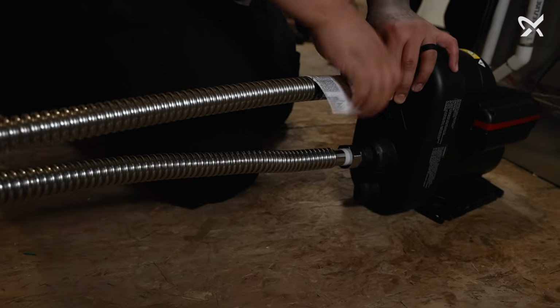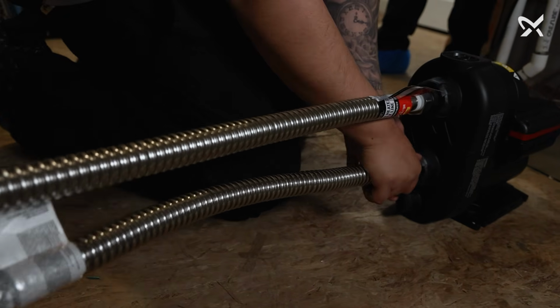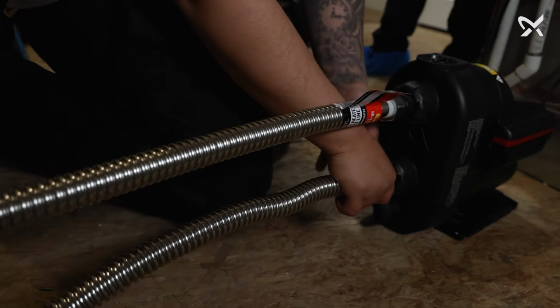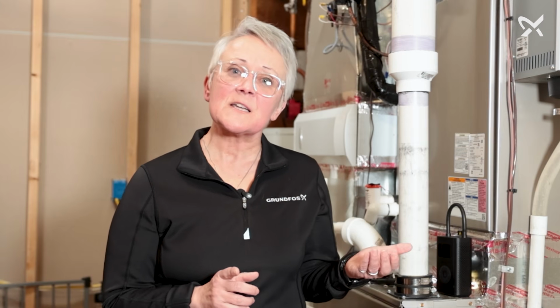So now we're on the topic of connections. We recommend the use of a 1-inch by 24-inch full port stainless steel connector. Although some people do choose to hard pipe this, flex connectors are the best option for you because they reduce the amount of sound due to vibration in the system. And when it comes to your connections, you want to make sure that there is at least 10 inches of straight pipe coming into the suction side of your SCALA. On a pressurized situation, we want a nice, smooth laminar flow.